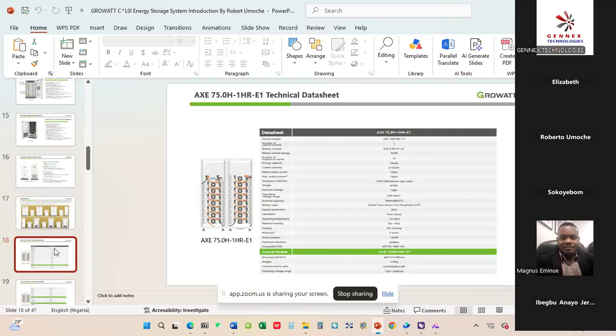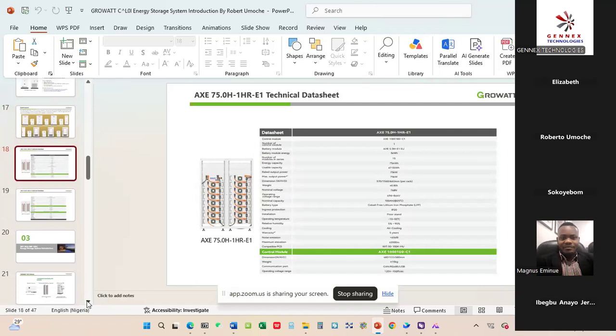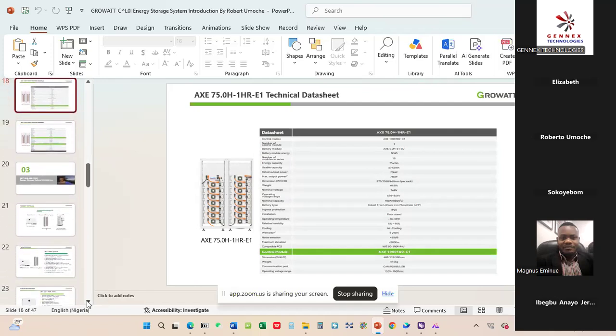Here we have the AXE battery, which is compatible with our WIT XHU model. These solutions are readily available in Nigeria, so if you need them you don't need to wait to have them supplied from China; as I speak to you, they are available. Each battery module, the HCE, is rated 5 kilowatt hours, and in this picture we have a total of 15 of them arranged on 2 different racks. The first rack has 8, and the next has 7 plus the battery management system, the BMS. If you multiply 15 by 5 kilowatt hours, you get 75 kilowatt hours in total for the 2 battery racks.